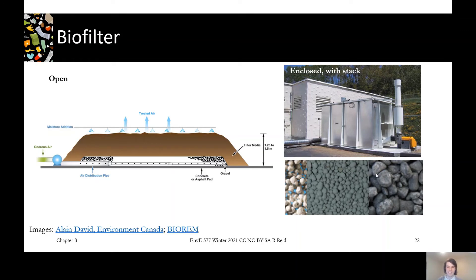This is just a baby one but this system is a little bit easier to control because it's all enclosed. It's easier to monitor and change the temperature and moisture and things like that and it might use a little bit more high-tech media than wood chips. These are some different ceramic media shown here that are specifically engineered to provide good surfaces for microbes to live on as well as for that water to flow over and be dissolving those odour compounds that are coming through the system. So biofilters are the types of systems that I've seen most commonly applied in Ontario and they just tend to be pretty reliable, pretty low-cost systems but you do have to keep the bugs happy or else they'll die and stop treating your odour.